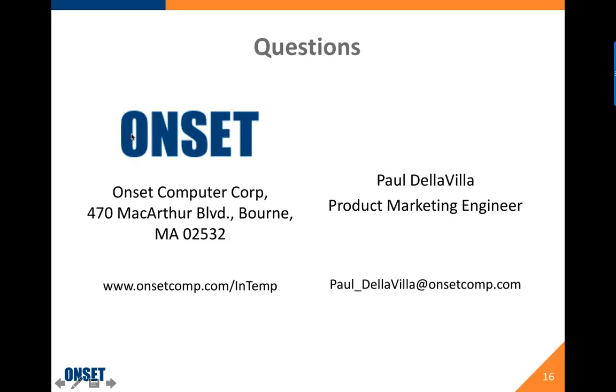All right. The last question, this is a really good one. How long are the calibration for the loggers? It depends on which loggers you're using. Our CX500 loggers and our CX400 loggers that are designated for good distribution practices in the pharmaceutical space have a 1-year calibration life. We do have CX400 loggers designed specifically for the VFC space that come with a 3-year certificate of calibration.